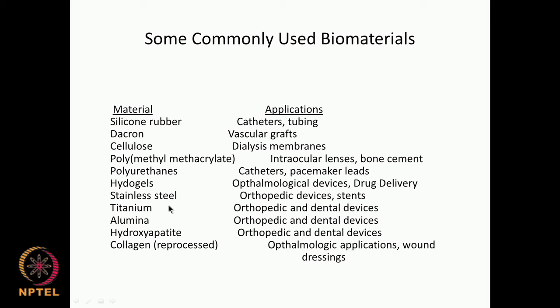Titanium is very biocompatible, used quite a lot in orthopedics, has good tensile and compressive strength, and is used in dental devices like screws. Alumina, as a ceramic or inorganic material, is very biocompatible and used quite a lot in dental devices. Hydroxyapatite — since our bone contains hydroxyapatite — is widely used in orthopedics, is extremely biocompatible, bones grow nicely especially after filling bone defects with it, and it is also used in dental devices and facial surgery. Collagen, derived from animals but reprocessed, is used in wound dressings and ophthalmological applications.